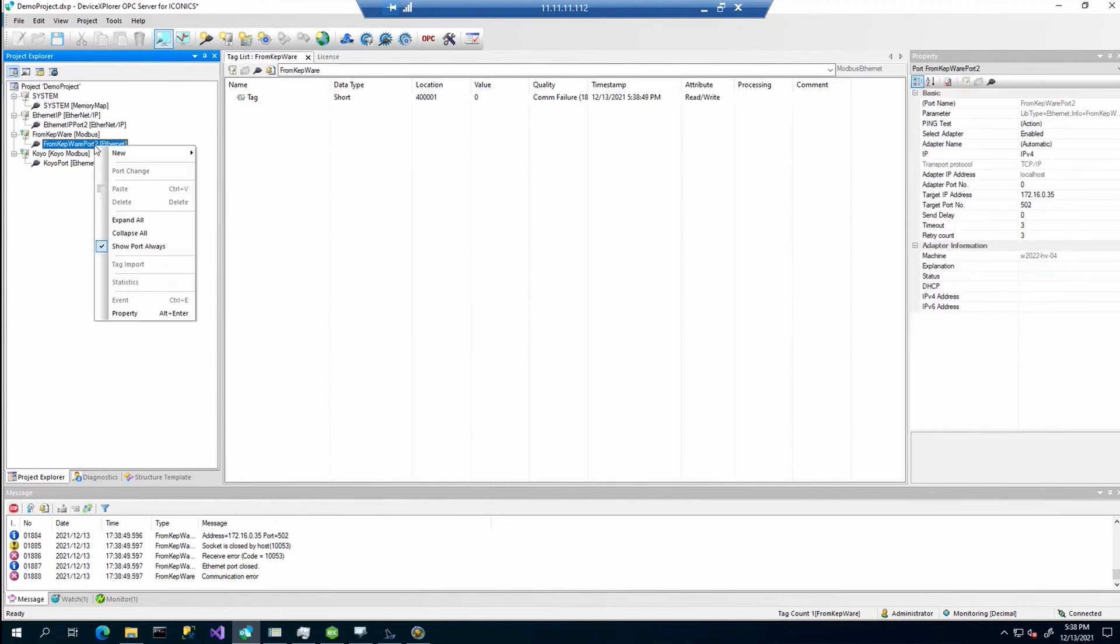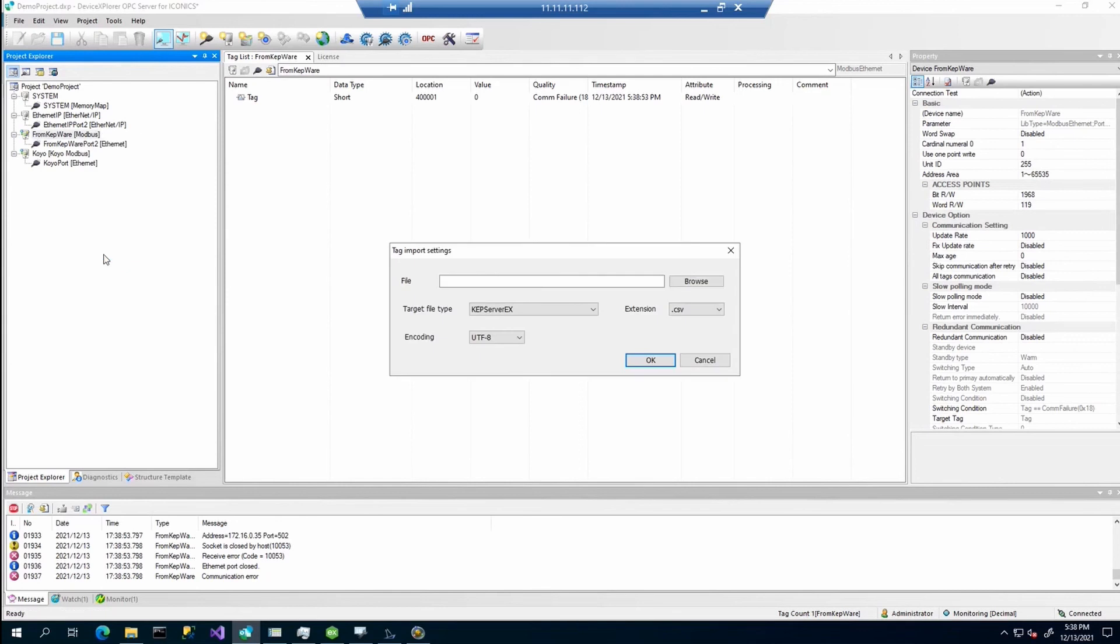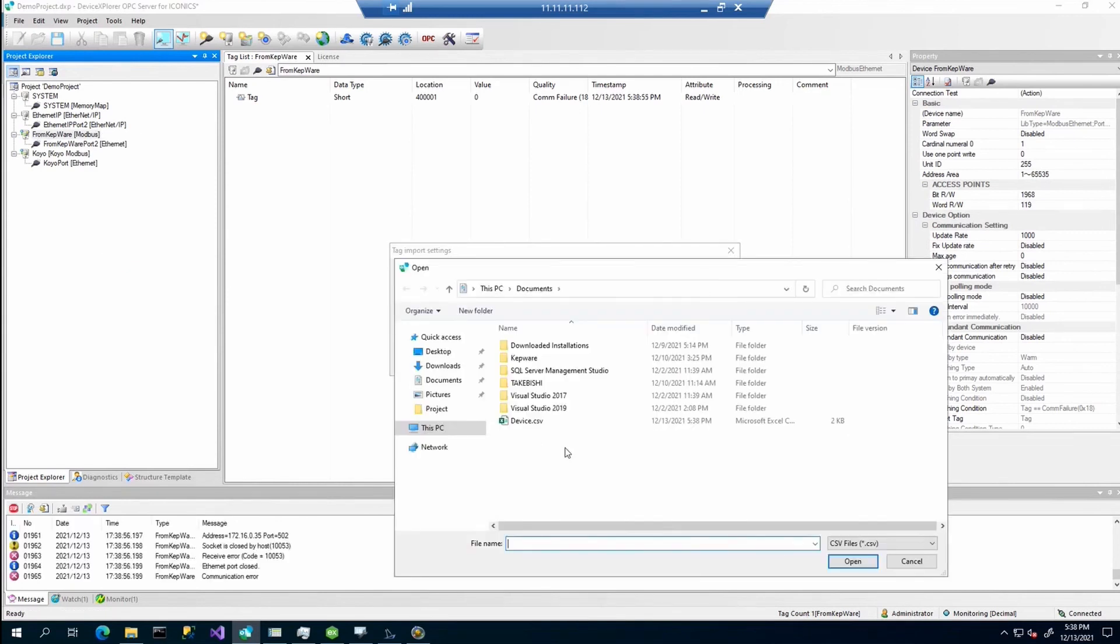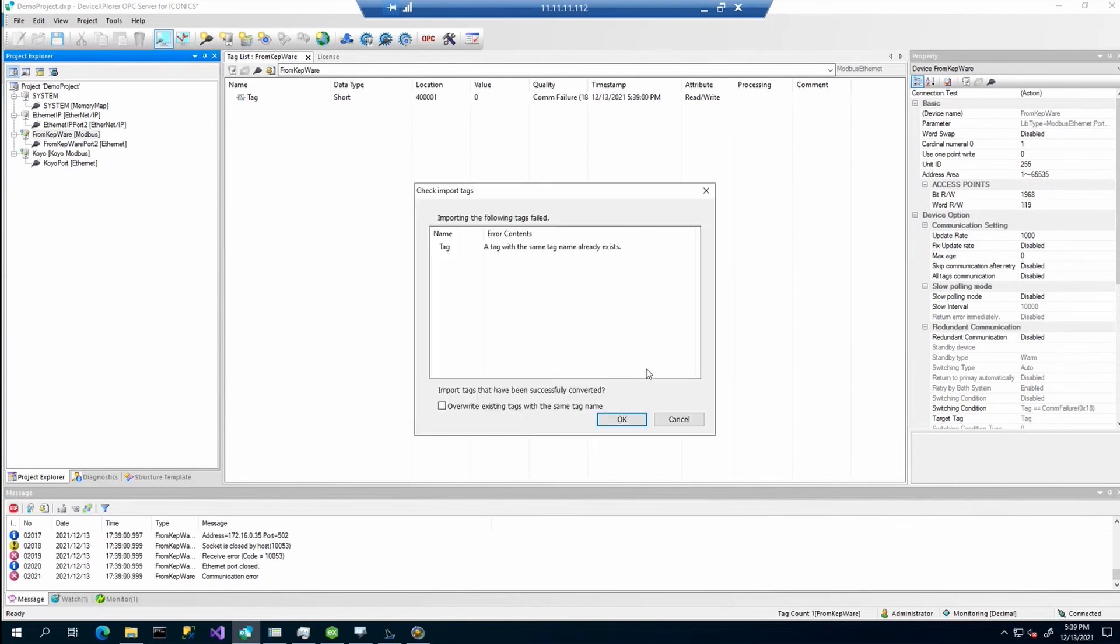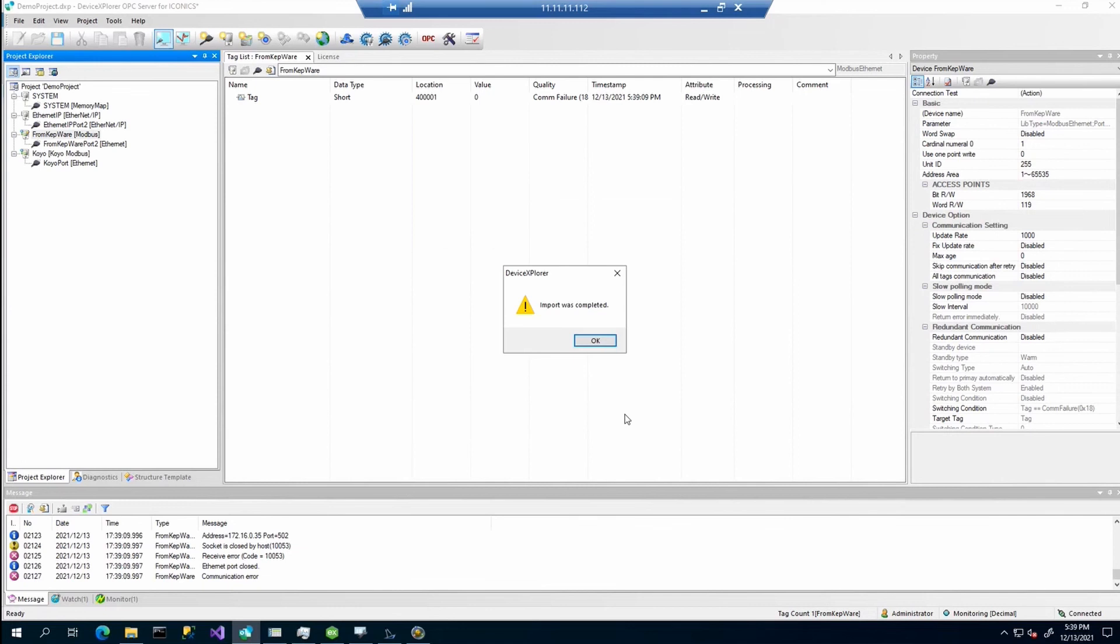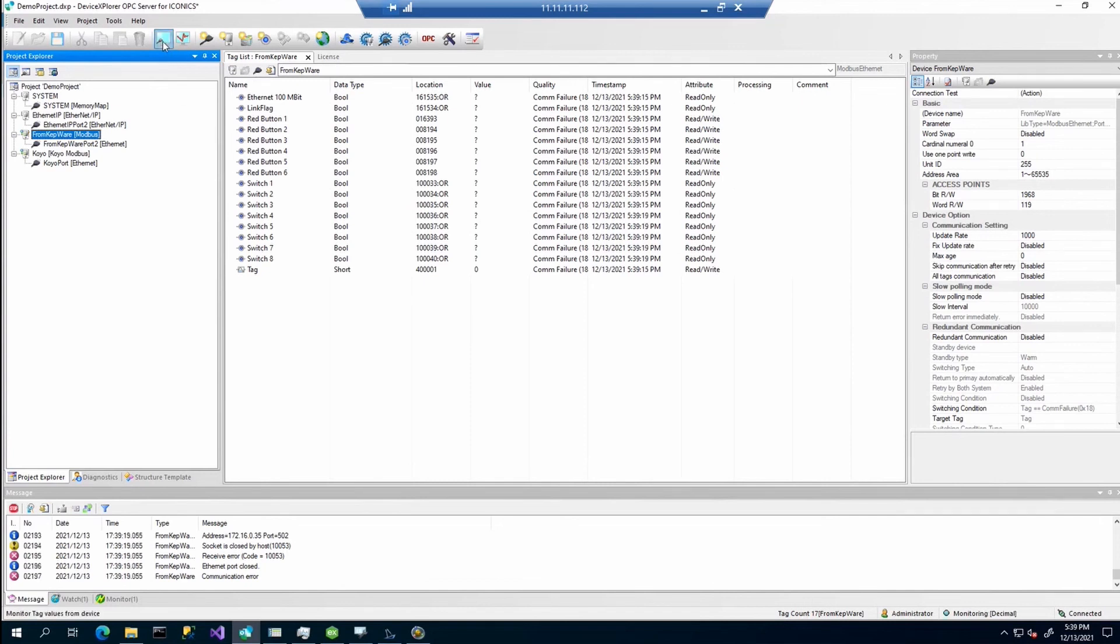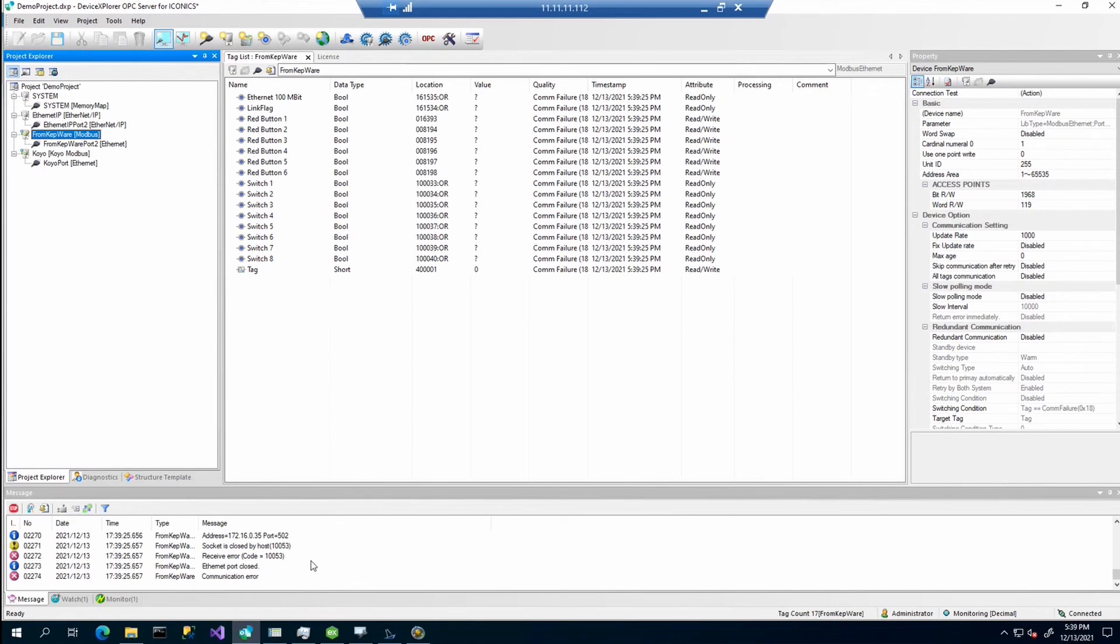Now we have prepared the project which is connected to the KEPServerEX. Right now we just need to right click on that project and select tag import. We will browse for the CSV which was created or was exported from KEPServerEX. Click OK. It can also detect that some tag was already pre-created. So we just simply check the override and click OK. It will import it. As you can see, we should get data. Unfortunately I cannot show it to you right now, maybe some port is closed. But basically it works. That's it from my site. Thank you.